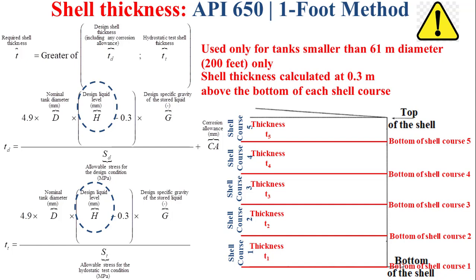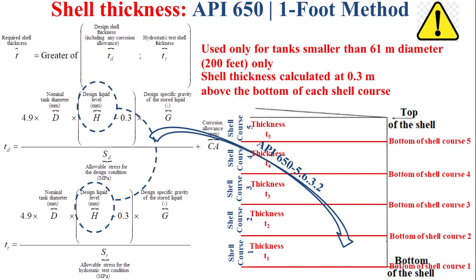The design liquid level h is the height from the bottom of the considered shell course to the top of the shell, so this design liquid level will vary depending on the considered shell course. For example, to determine the thickness t1 for shell course 1, we use h1, which is the height from the bottom of shell course 1 to the top of the shell, to determine td1 and tt1.